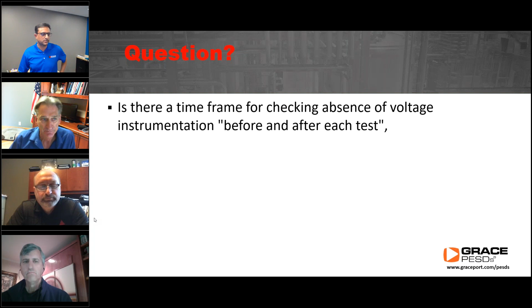After looking at the question again, I'm wondering if somebody was thinking, we did the live-dead-live test an hour earlier, now do I have to test again when I get into another cabinet or another piece of equipment? Do I have to test the voltage test instrument again? And the answer is yes. You're testing the test instrument right before testing for absence of voltage, phase to phase and phase to ground of each conductor and circuit part, then testing the test instrument again. Even 20 minutes later when you go to another piece of equipment, you go through the same steps every single time. You don't get to say I've tested my test instrument once today, I don't need to do that again. Yes, you do.